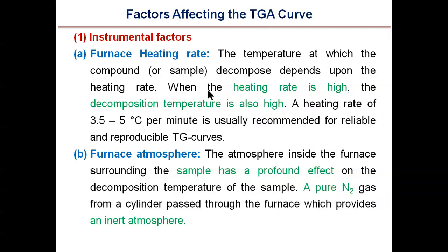The furnace atmosphere, that is the atmosphere inside the furnace surrounding the sample, has a profound effect on the decomposition temperature of the sample. Pure nitrogen gas from a cylinder is passed through the furnace, which provides an inert atmosphere surrounding the sample.